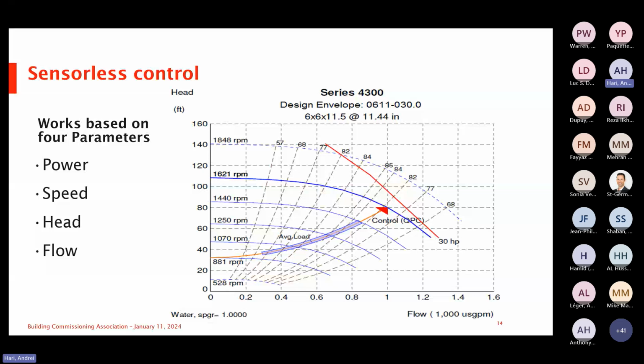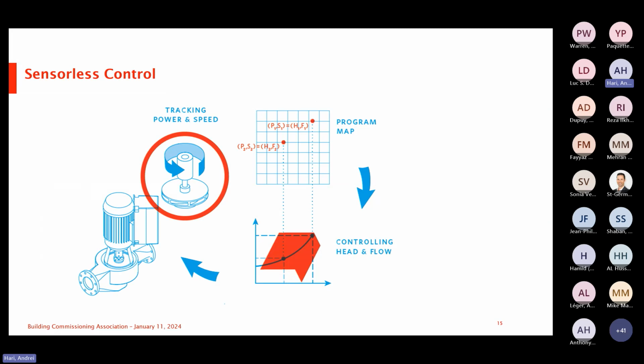So we are using that function, or understanding that function, in how we're operating sensorless control. The way it's done is that we're tracking the power being drawn by the motor and the speed of rotation it's at. And based on that power and speed, we have that equated to a flow and a head.